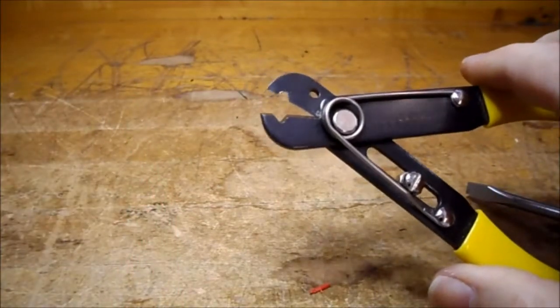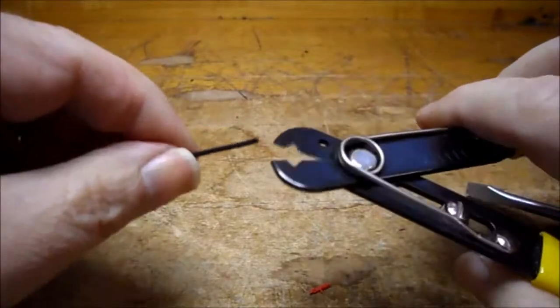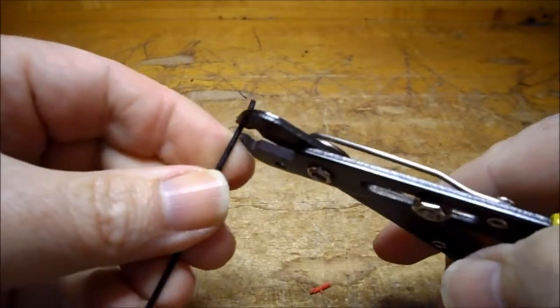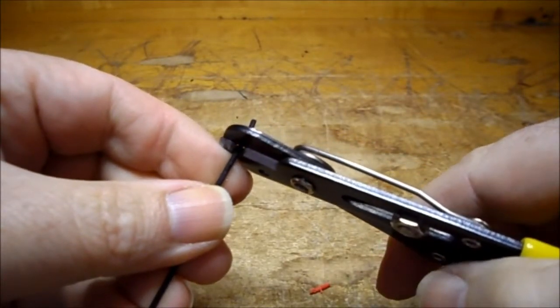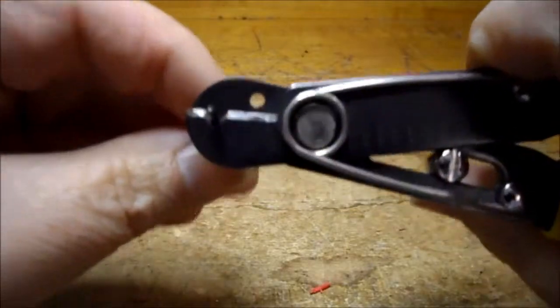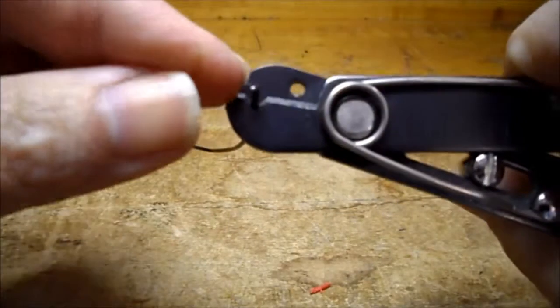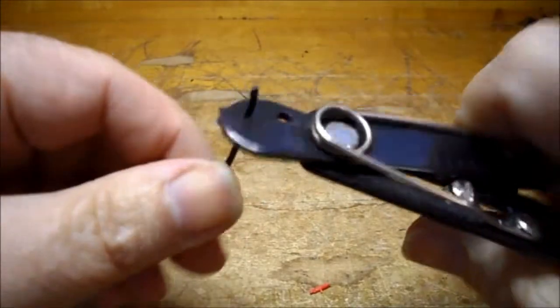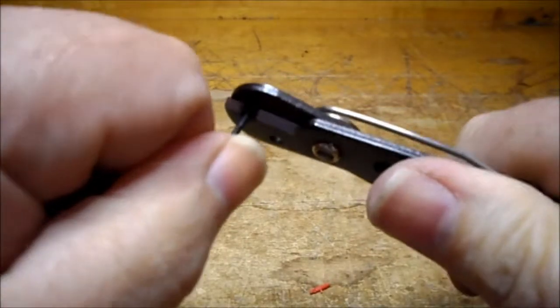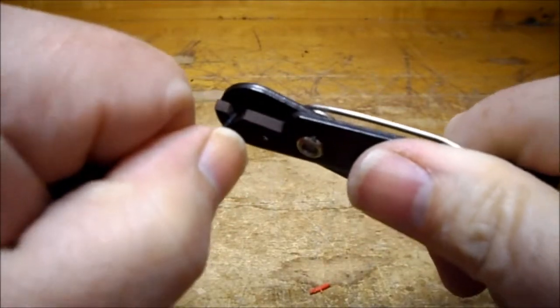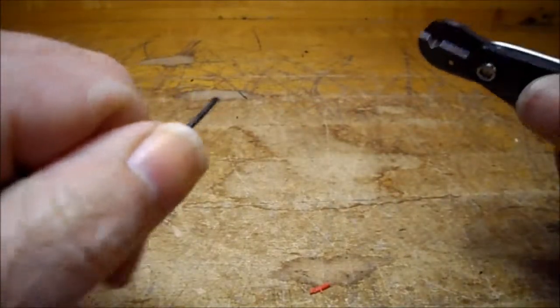So now when you take a piece of wire with the insulation on it, you should be able to bring it in and close. Notice how it holds the wire because it's actually dug into the insulation. Then just hold onto your piece of wire firmly and push away with your wire stripper. You can see that makes a nice clean cut on your insulation and it doesn't nick the wire.